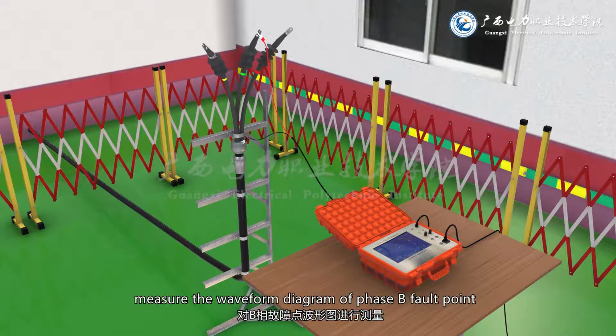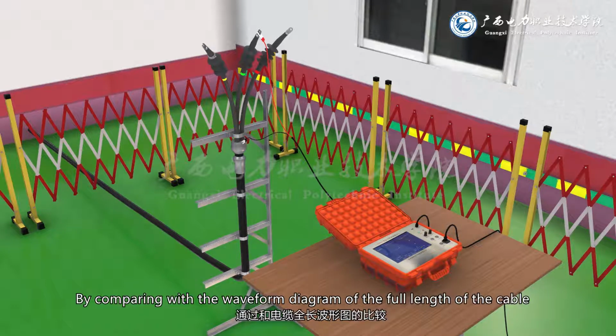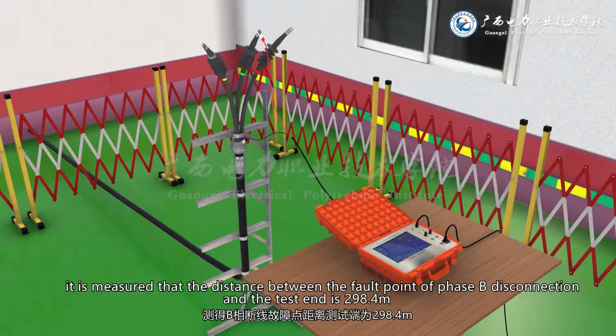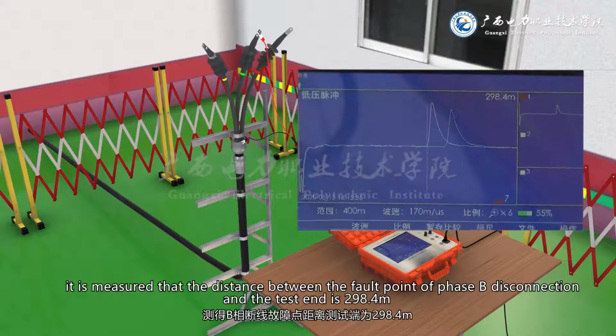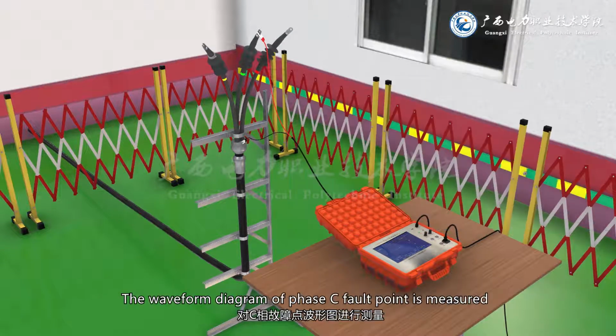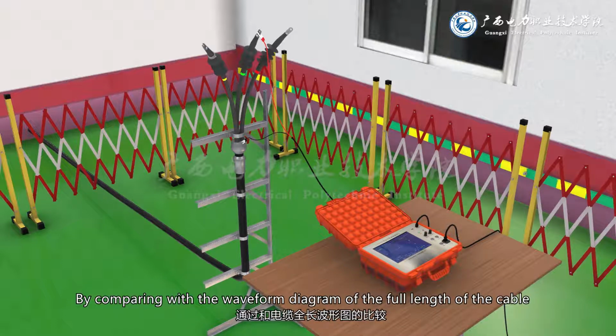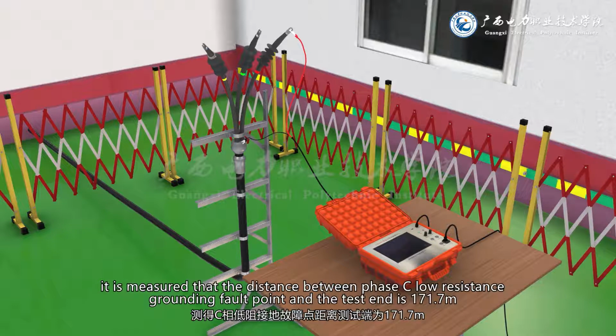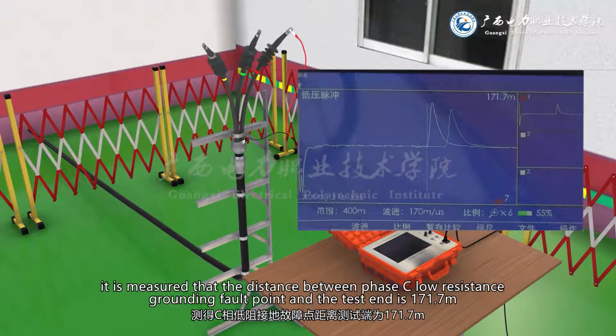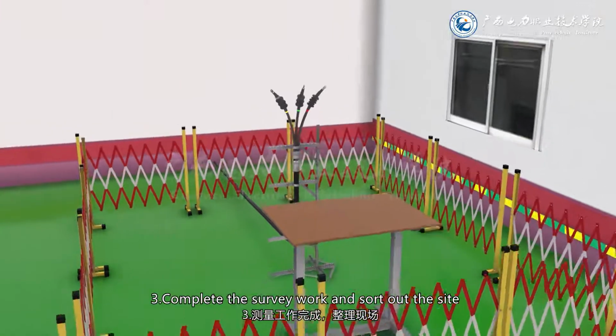Measure the waveform diagram of the phase B fault point. By comparing with the waveform diagram of the full length of the cable, the distance between the phase B disconnection fault point and the test end is 298.4 meters. The waveform diagram of the phase C fault point is then measured. By comparison with the full-length waveform, the distance between the phase C low-resistance grounding fault point and the test end is 171.7 meters. 3. Complete the survey work and tidy up the site.